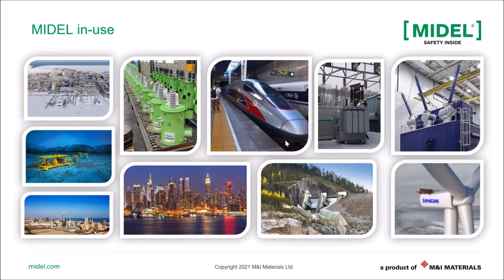The fastest trains around the world use MIDEL esters as well in their traction transformers. When we think of applications, this is probably the most intense application for transformers because these are high temperature transformers. The trains have to go from zero to high speed in a few seconds, so the transformer has to energize very quickly and it has to be able to handle the load.